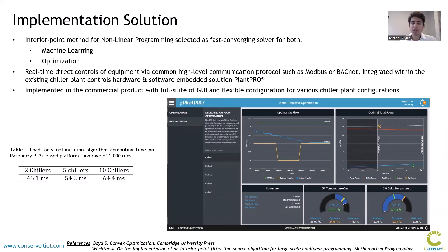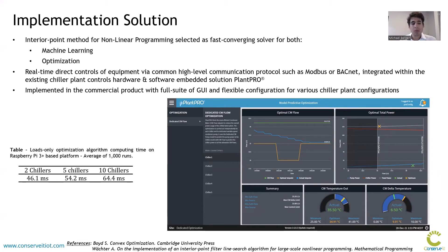The machine learning was also designed to run regularly over time so that it captures performance variation in equipment, especially performance degradation, and adapts the optimization accordingly. The solution was designed for real-time direct control of equipment using common high-level communication protocols, and to be integrated within an existing chiller plant controls hardware and software solution called PlantPro, leveraging that existing platform and focusing on the optimization. After several prototype iterations and site trials, it was implemented as a commercial product with a full suite of user interfaces and flexible configuration for various chiller plant configurations.